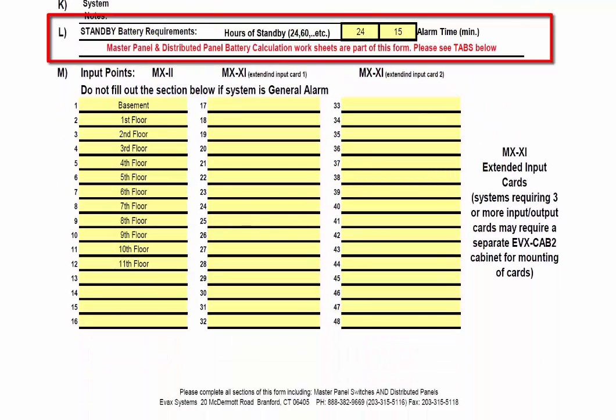Item L, Standby Battery Requirements. The hours of standby are typically defaulted to 24 hours and 15 minutes of alarm time. If you choose to change this, you can do so in this section. Also note that the Master Panel and Distributed Panel Battery Calculation Worksheets are also a part of this form.